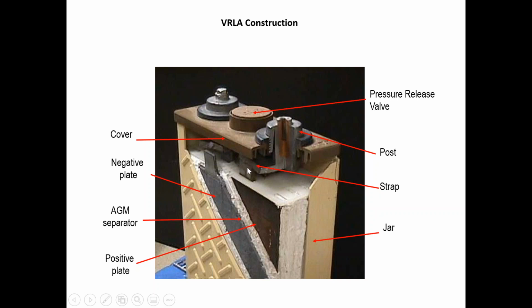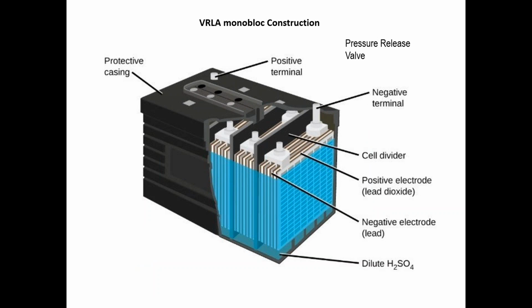So there's the straps. Again, this is where you can actually see quite a bit of potential issues with the battery, corrosion, and things of that nature happen here. But again, typically you can't see it. And I'll show you how we do actually as part of our preventive maintenance look at those straps, but I'll show you some of that a little bit later. And then this is the monoblock. I'm missing the arrow. But the pressure relief valves are actually usually seated under the cover. Sometimes you'll see them, sometimes you won't. This is a 12-volt battery, so it's 6 cells in series, usually with a positive and negative terminal, 12 volt. Again, positive and negative plates, separators, very similar material to the previous battery, just assembled into a smaller monoblock.